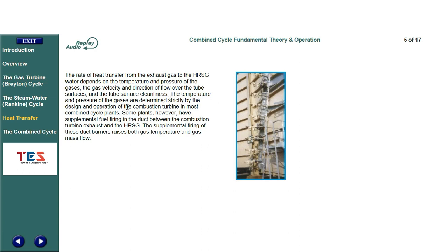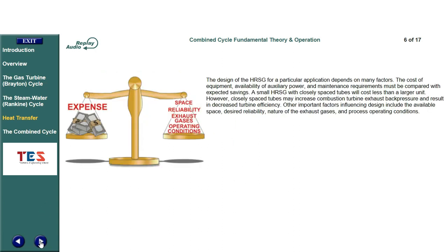The temperature and pressure of the gases are determined strictly by the design and operation of the combustion turbine in most combined cycle plants. Some plants, however, have supplemental fuel firing in the duct between the combustion turbine exhaust and the HRSG. The supplemental firing of these duct burners raises both gas temperature and gas mass flow. The design of the HRSG for a particular application depends on many factors. The cost of equipment, availability of auxiliary power, and maintenance requirements must be compared with expected savings. A small HRSG with closely spaced tubes will cost less than a larger unit.